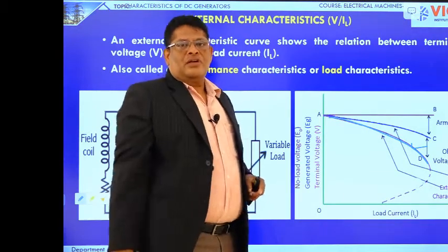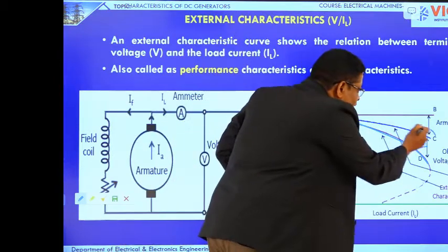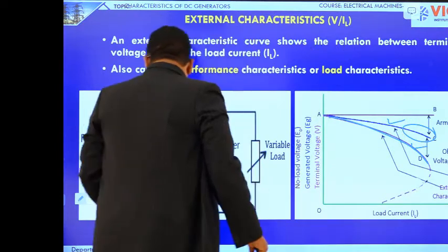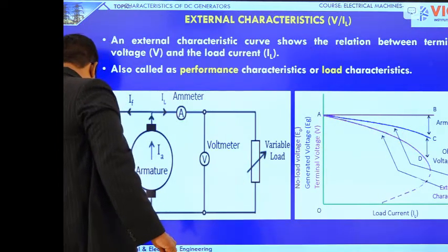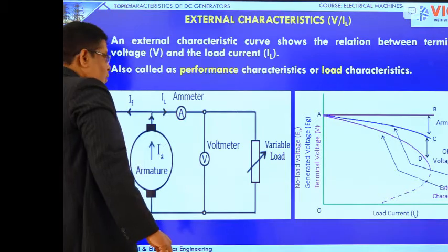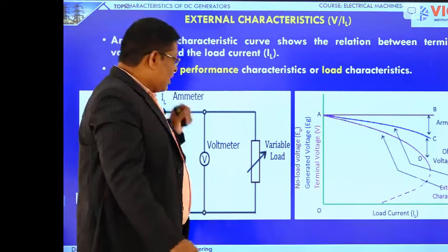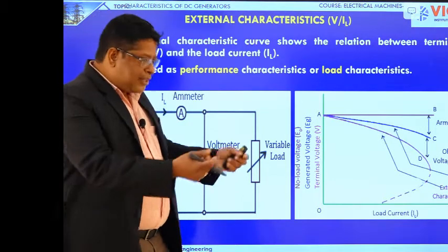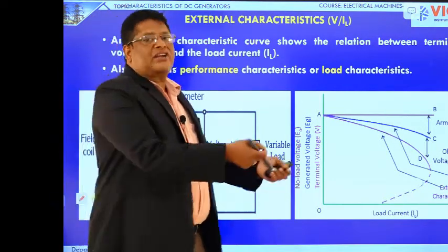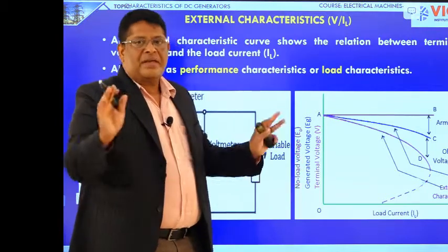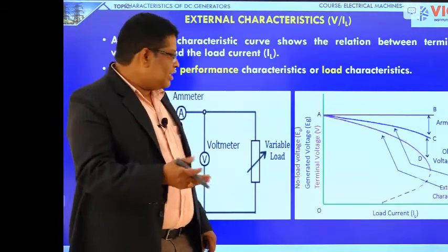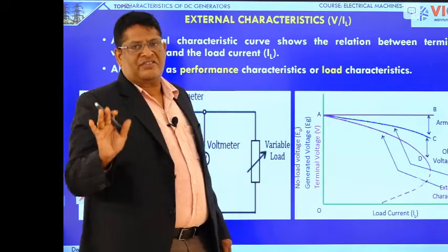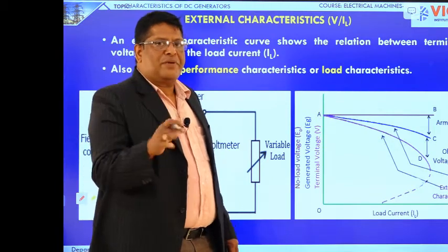How are we getting the second graph? We know the armature current is nothing but the load current. In the same manner, we know the armature resistance also. Take a multimeter and connect it across the armature terminals directly to give the reading. For a well-designed machine that will be less than 1 ohm. For a badly designed machine, that resistance will be near 2 ohms.